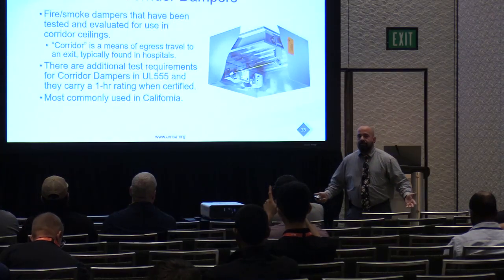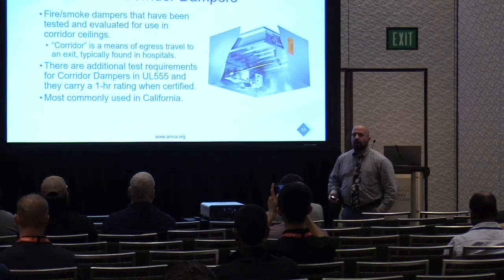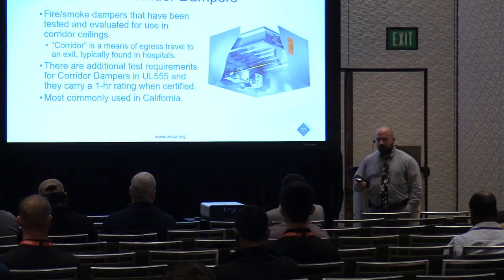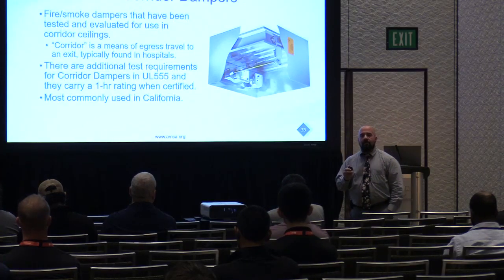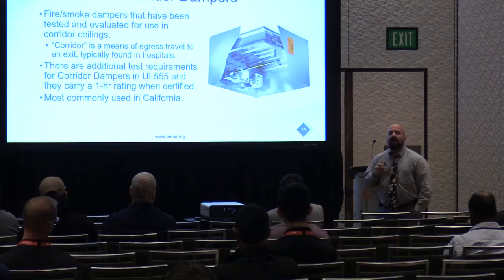There's nothing wrong with that. They just need to be applied correctly. There's a specific installation for them. So if anybody outside of California is interested in corridor dampers, take a look at your installation instructions for fire smoke dampers. They're not the same as your regular fire smoke damper.